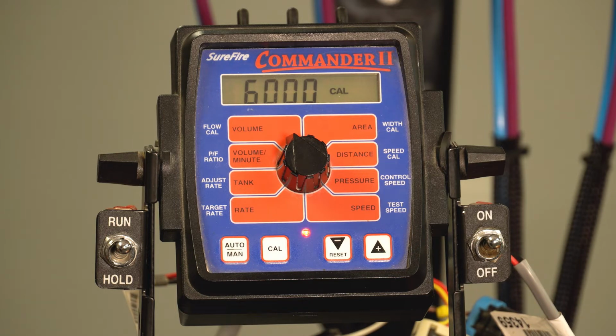Again, very simple here. This is where we would enter the calibration number for your flow meter. There are several different flow meters across the board, but again, in this scenario, we're using our 0.3 to 5 gallon per minute electromagnetic flow meter from Surefire Ag, which requires a 6,000 pulses per gallon number.